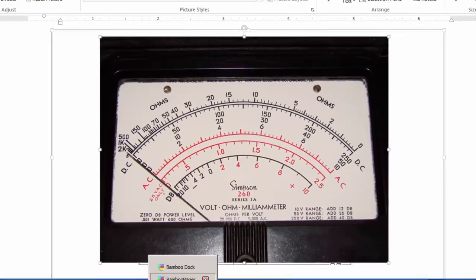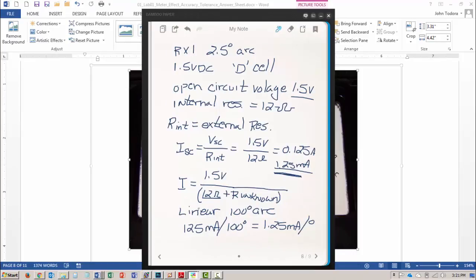I can go further than that now and say that because my tolerance is 2.5 degrees of arc, I can calculate the current that's required to make the meter move 2.5 degrees. And that can be easily done by saying 2.5 degrees times the 1.25 milliamps per degree, which comes up to 3.125 milliamps. So for 2.5 degrees of arc, knowing that I'm at 1.25 milliamps per degree, for every 2.5 degrees of arc, I have 3.125 milliamps. That's important information for us to know.